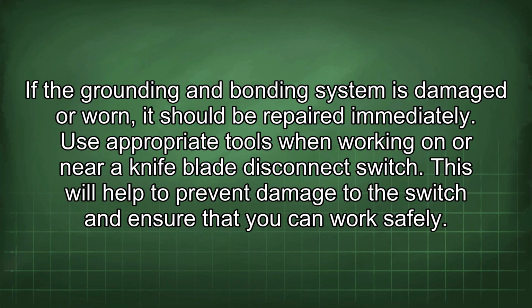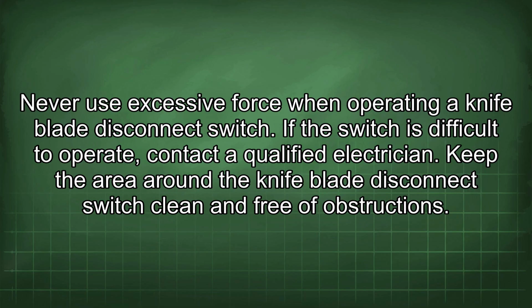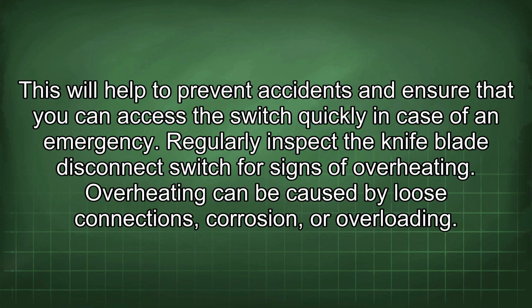Use appropriate tools when working on or near a knife blade disconnect switch. This will help to prevent damage to the switch and ensure that you can work safely. Never use excessive force when operating a knife blade disconnect switch. If the switch is difficult to operate, contact a qualified electrician. Keep the area around the knife blade disconnect switch clean and free of obstructions. This will help to prevent accidents and ensure that you can access the switch quickly in case of an emergency.